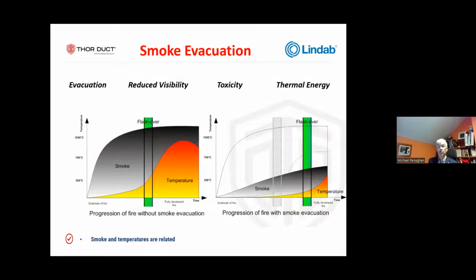So you guys are going in, or you're sending crews in to fight this fire. You're going in to fight it, but it's hotter than it should be because the smoke is not getting away. And the smoke is not stifling the fire, it's containing the heat. It's exacerbating the heat. If you have a smoke evacuation system, the flame temperature doesn't change. However, the temperature within the environment of the fire radically changes. So it's very important to have the smoke evacuation system working. So that does make a difference.